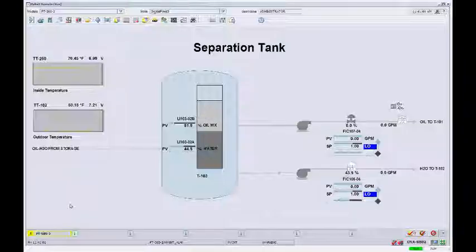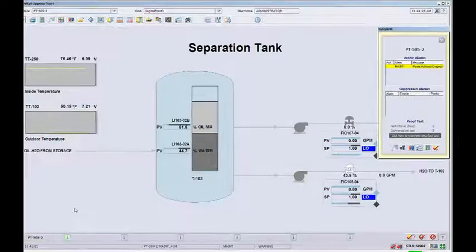When the 3051S detects wiring corrosion or other connectivity problems, it sends a PlantWeb alert to the logic solver using the HART protocol. Because DeltaV SIS has HART integrated I/O, the alert is visible on the DeltaV alarm banner.